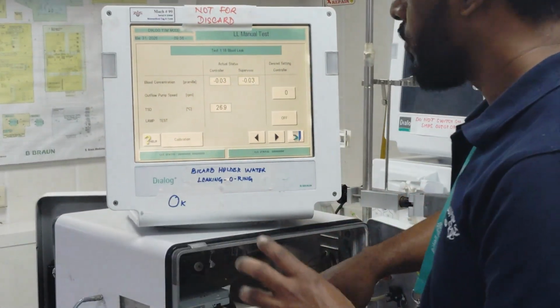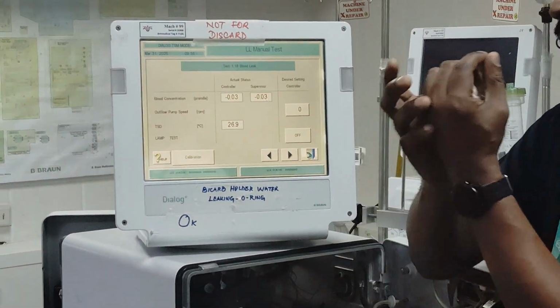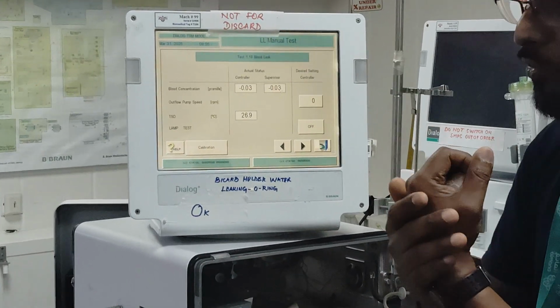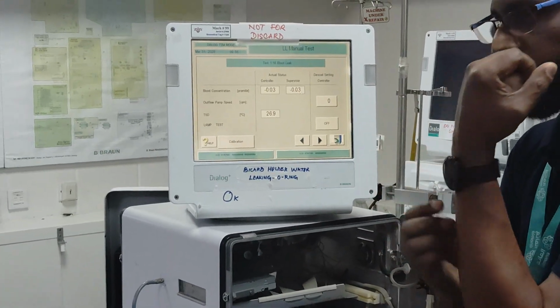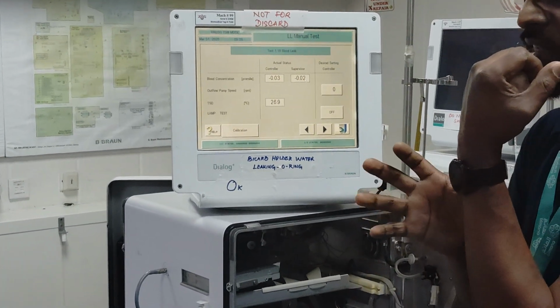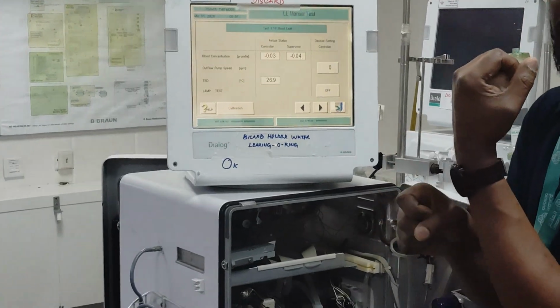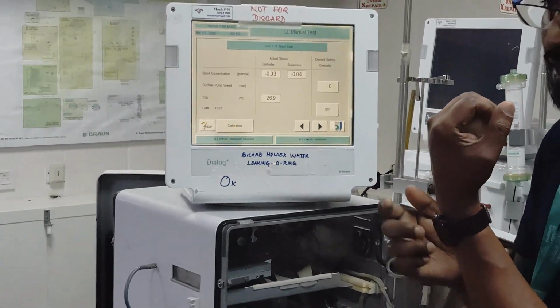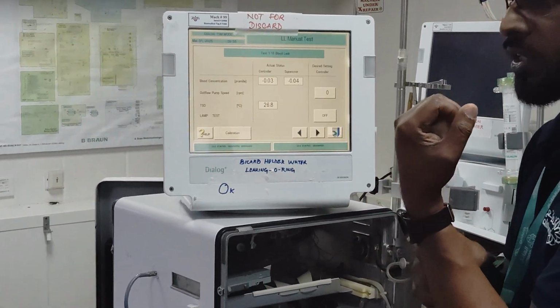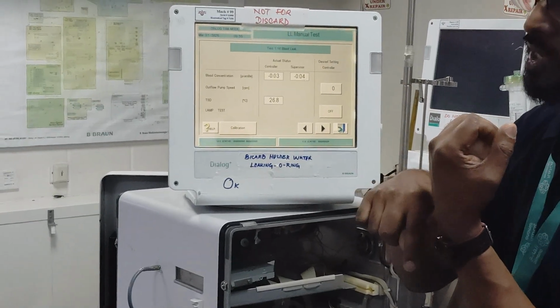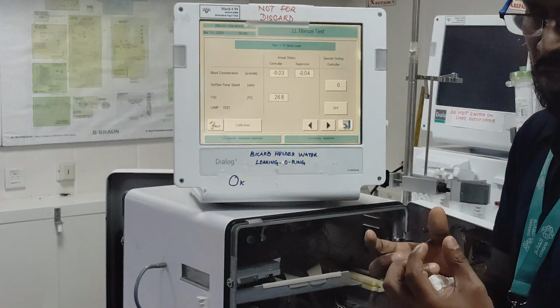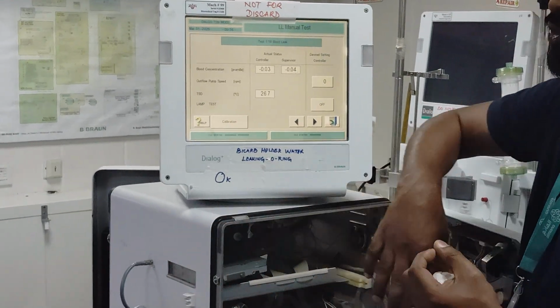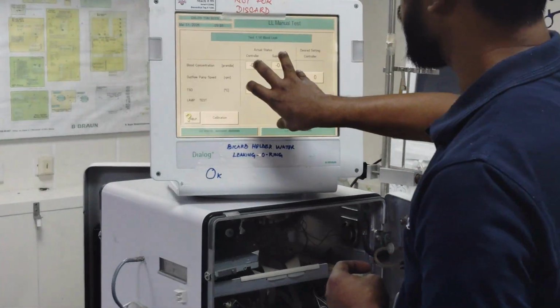During dialysis, the patient's body fluid can mix with the blood and come there. Just for the safety side, we have to keep the blood leak, so it will make an immediate alarm. Your blood is leaking. Whether it's real leaking or not, we have to check that. The real leaking means sometimes the filter is having issues, spotted over there, and blood is trying to pass through that water. So that can be checked over there.